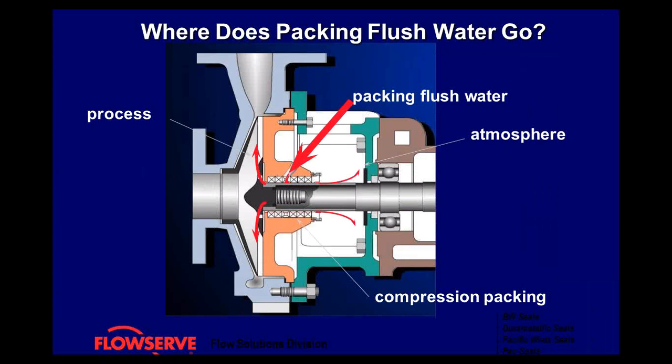Where exactly does the packing flush water go? Packing has to be lubricated because it is in contact with the shaft. Usually there's a lantern ring where the flush water can be applied. That water has to leak into either the process or to atmosphere, so that it can lubricate and cool that shaft.